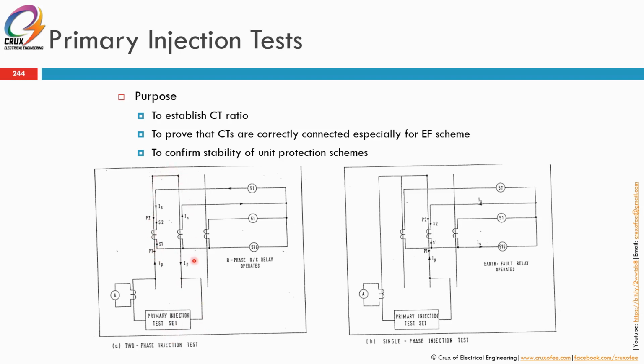So the overcurrent for the red and yellow will pick up. Blue will not, because there's no current. So if one of the CTs is in reverse connection, S1, S2, or the primary connection is reversed, the summation point between red and yellow will not be 0. The current will become double and may trigger 51G. So indirectly you can check whether the earth fault connection is correct or not.